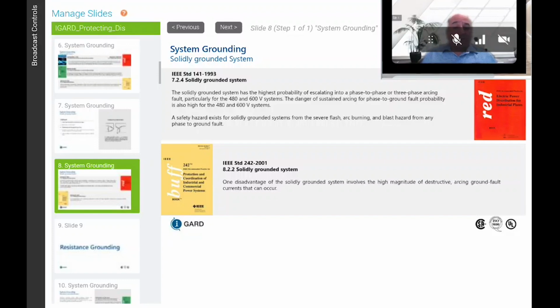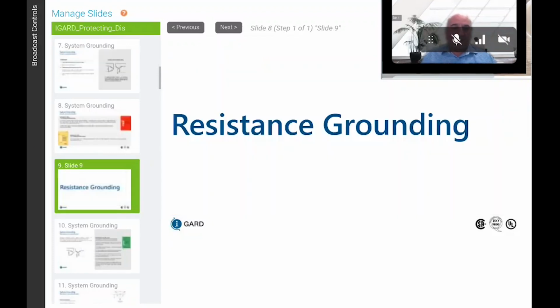A safety hazard exists when you have a solidly grounded system for severe arc flash and arc burning, because a ground fault can occur anywhere in your facility. If you're working near the equipment where the ground fault occurs, you could be subject to an arc flash event. This is why people have to wear PPE when they're working on or near electrical equipment. A disadvantage of a solidly grounded system involves the high magnitude of destructive arcing ground fault currents. And when you have a high magnitude of destructive arcing ground fault currents, you have the possibility of a phase-to-phase fault derived from that single phase-to-ground fault.